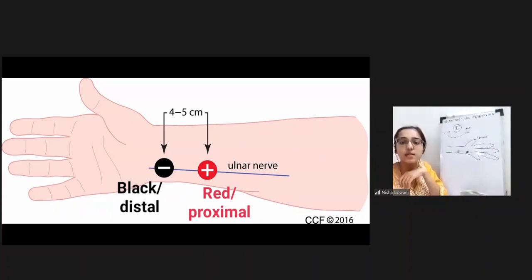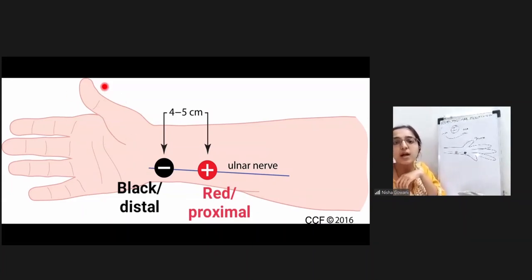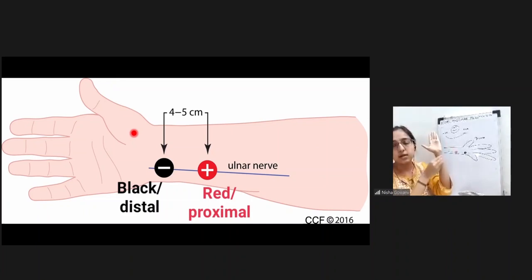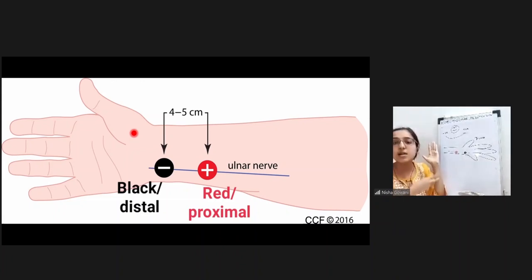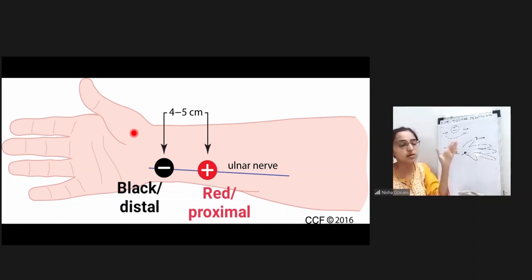You can see the patient's thumb - we expect adductor pollicis to do adduction. The black electrode is placed distally and the red proximally along the course of the ulnar nerve. When current passes between positive and negative, the ulnar nerve gets stimulated and adductor pollicis - supplied by the ulnar nerve - produces adduction.